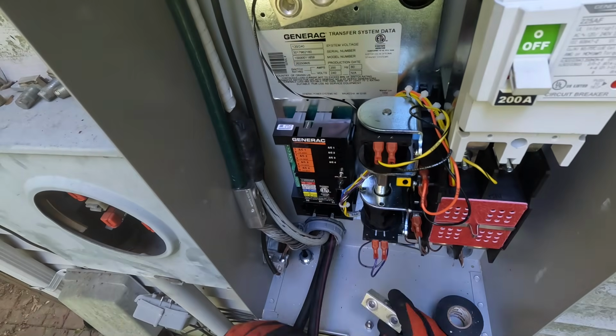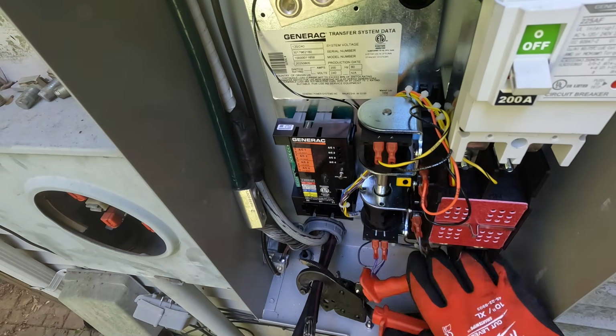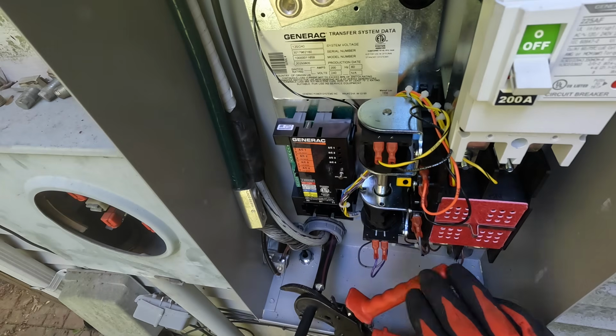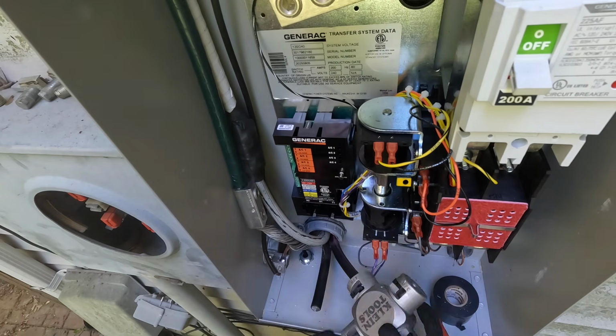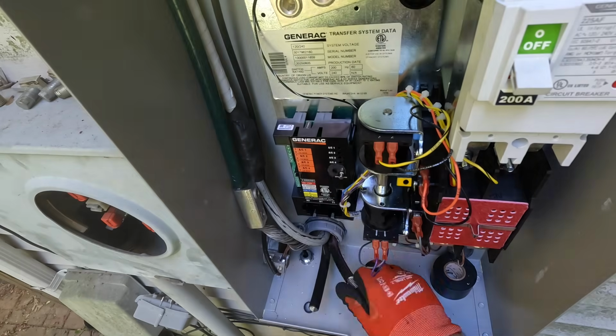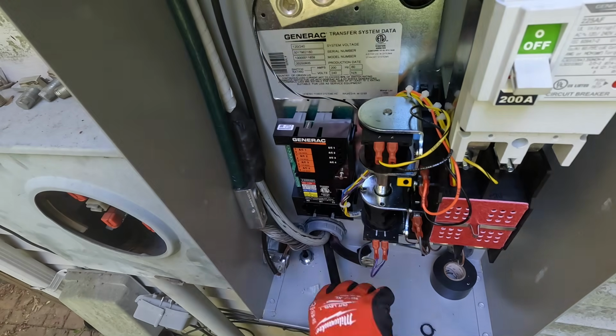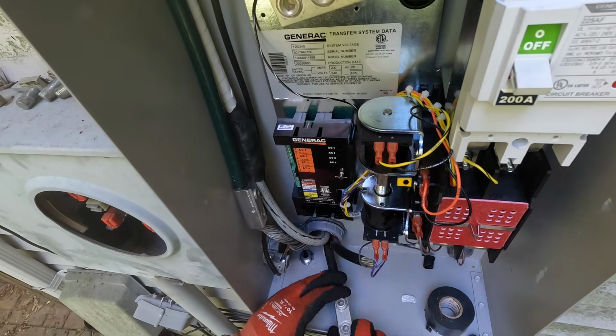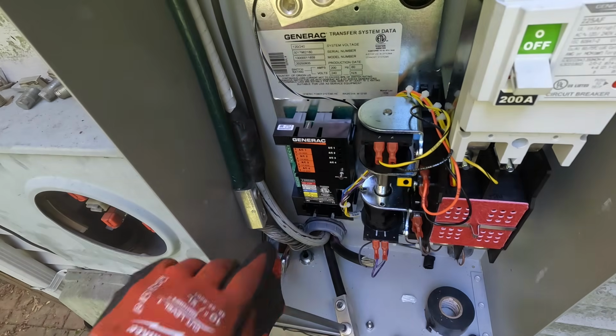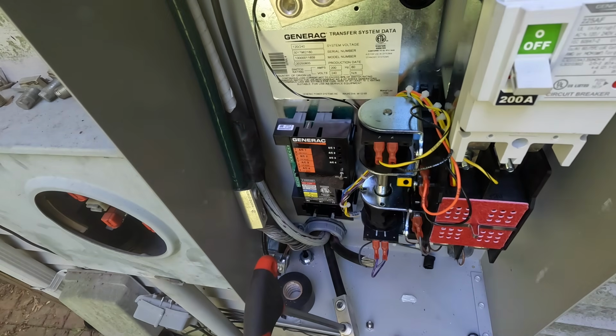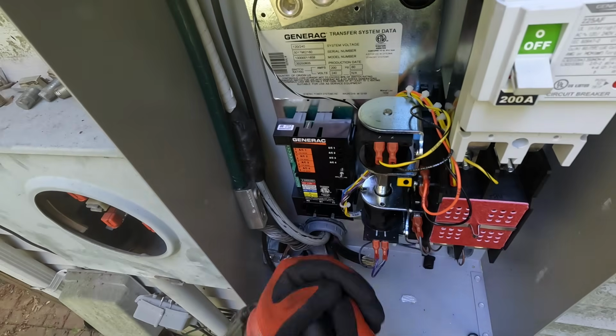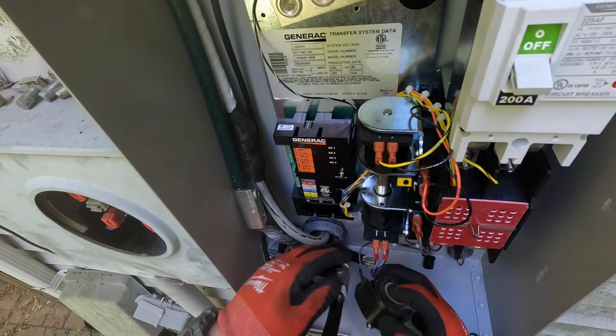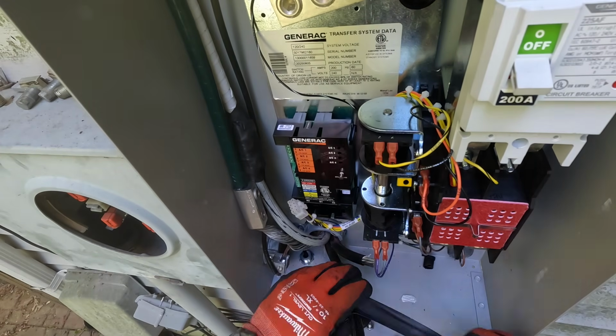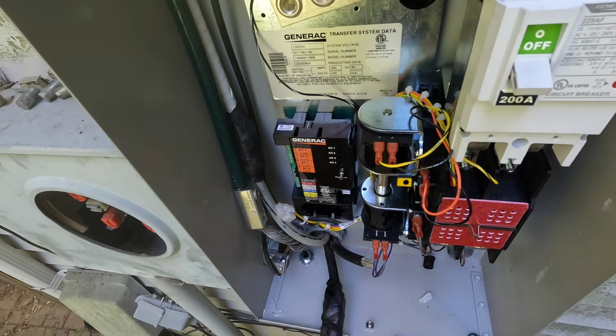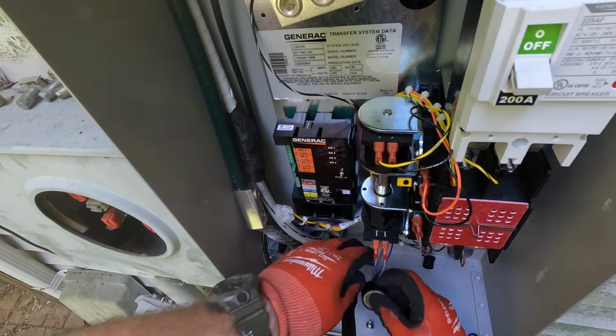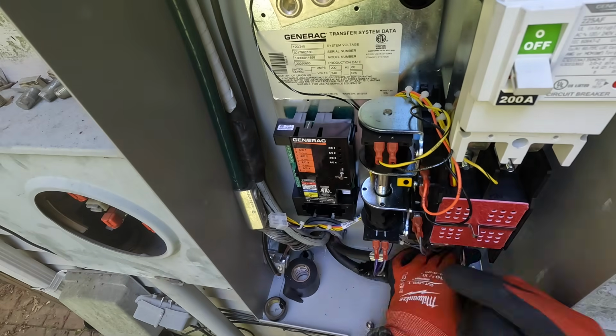So all that this transfer switch does is it senses when utility power has been lost, and then it sends a message to the generator to start up. When the generator is ready and the voltage is being supplied accurately, it sends another message back to the transfer switch to switch from the utility side to the generator side. That's that little yellow button in the middle there. There's two different coils, one up on the top, one on the bottom, to make this connection and to transfer between the generator source and the utility source.